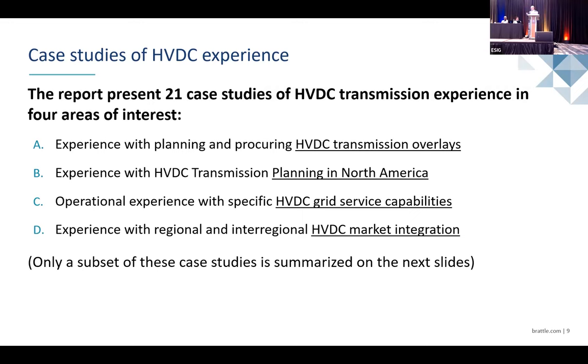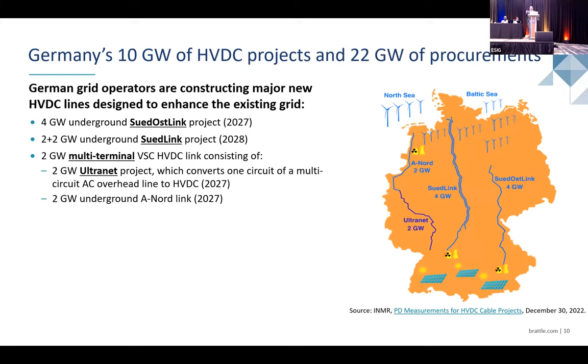I'll just give you a couple examples. One is in Germany. Germany is currently in the process of constructing about 10 gigawatts of HVDC projects between Northern Germany, wind-rich area, and Southern Germany, solar-rich area. These are all sort of 2 gigawatt systems that will come online over the next several years. One of them, the Ultranet project, is particularly interesting because they are replacing one circuit of a multi-circuit AC line with DC technology, so they can use the same wires, the same towers. They need new insulators, but other than that, they can just, you know, triple the throughput capacity on that circuit by converting it to DC overhead. A lot of them are underground because of permitting issues.